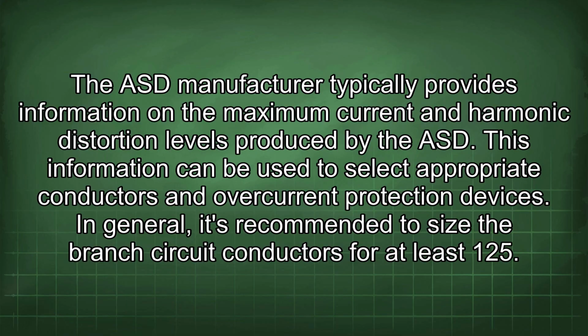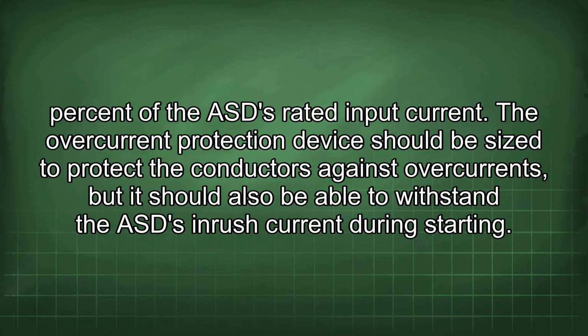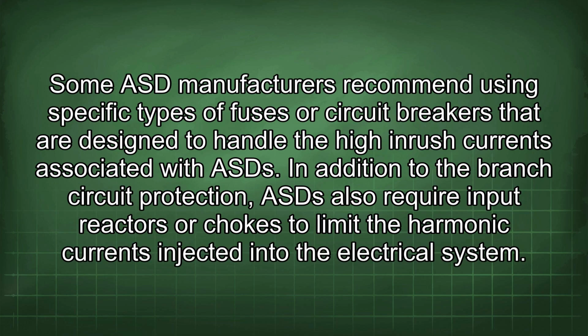In general, it's recommended to size the branch circuit conductors for at least 125% of the ASD rated input current. The overcurrent protection device should be sized to protect the conductors against overcurrents, but it should also be able to withstand the ASD inrush current during starting.